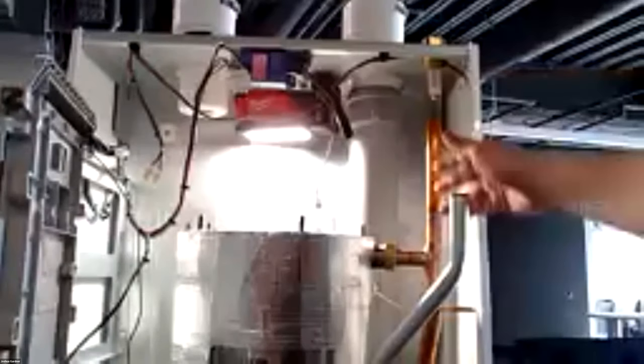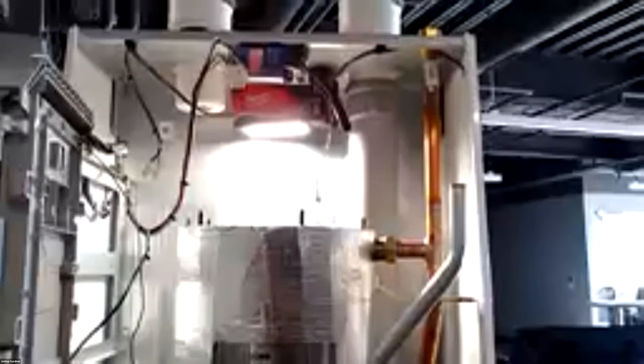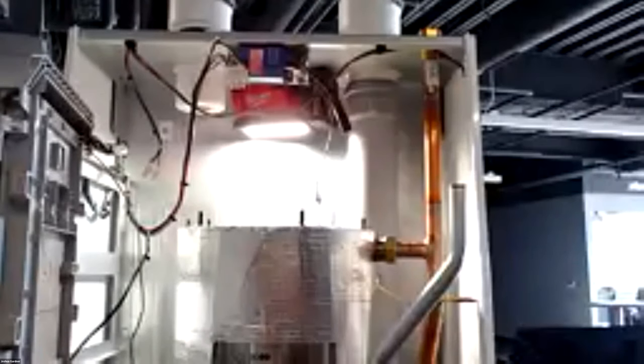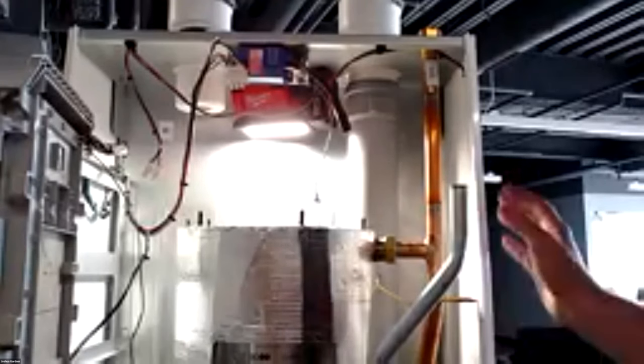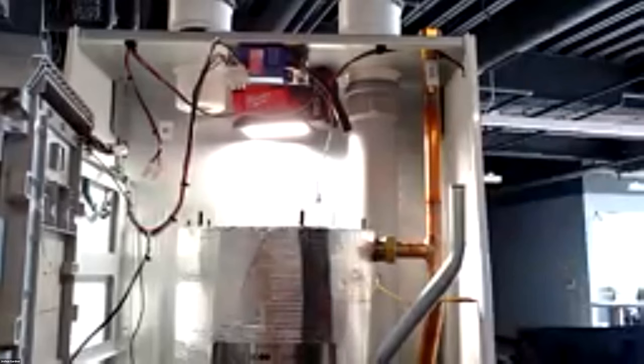Go through, visually inspect the unit, see if you have any leaks. Anything doesn't look right. That's really the big thing, is making sure we don't have like the high vent leaking and that drips down, drips in the sensor, kills the sensor. Those are usually the killers on high efficiency boilers, is there a leak somewhere and that leak dropping something out. Not big on our boiler because we have a lot of space in here, but some other manufacturers where everything's jammed right in there, that's typically what happens. We have that water leaks down and it goes everywhere. So just be mindful of that.